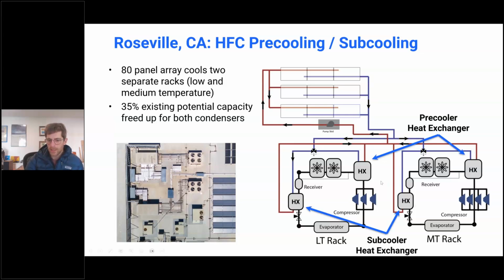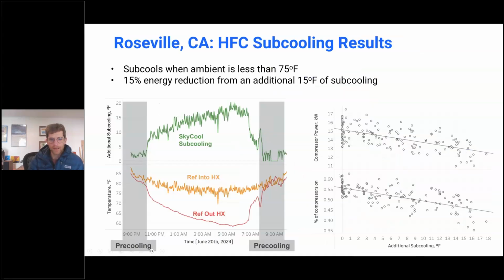And so here you can see the heat exchangers. We had 2 subcooling heat exchangers, 1 per rack, and then pre-cooling heat exchangers after the compressors before the condensers. But in this particular system, we're subcooling the refrigerant when the ambient is less than 75 degrees, and that gave about 15% improvement to the efficiency of the system. So you're getting more cooling capacity with that refrigerant now, and so fewer compressors actually need to run, and that's why you see less power being drawn by the compressors.